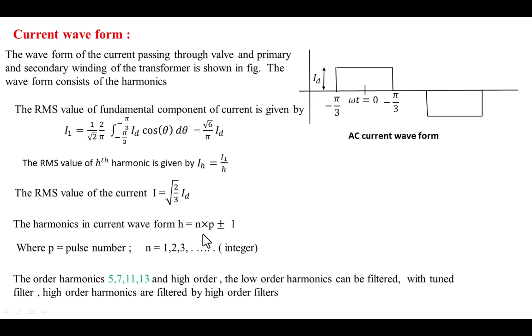The harmonics present in this current waveform are of order H = N × P ± 1, where P is the pulse number and N is an integer. For this converter, the pulse number is 6. So if N = 1, we get the 5th and 7th harmonics. If N = 2, we get the 11th and 13th harmonics. Next we get the 17th and 19th, and so on. These are lower-order harmonics. We can filter them out using tuned filters or damped filters connected to the primary winding of the transformer to eliminate these harmonics. Higher-order harmonics can be eliminated using high-order filters.